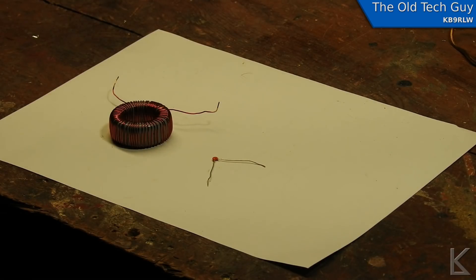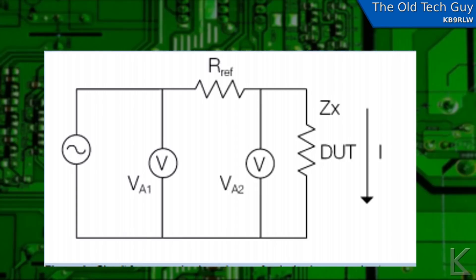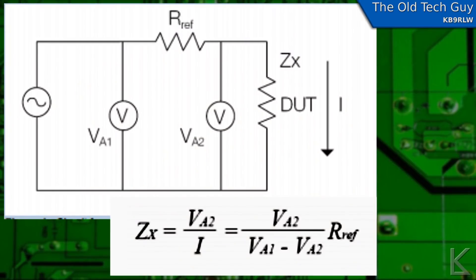Back to this test jig. The reference resistor is a known resistance — you need to measure it and know its value precisely. What you're basically setting up is a resistor divider network: you've got your unknown impedance on the device you're measuring and a known resistance, and you're going to measure the voltage drop across the known resistance. You take a voltage measurement on the input and the output of it, and once you've got that voltage drop you have all the information you need to calculate what the unknown impedance is.